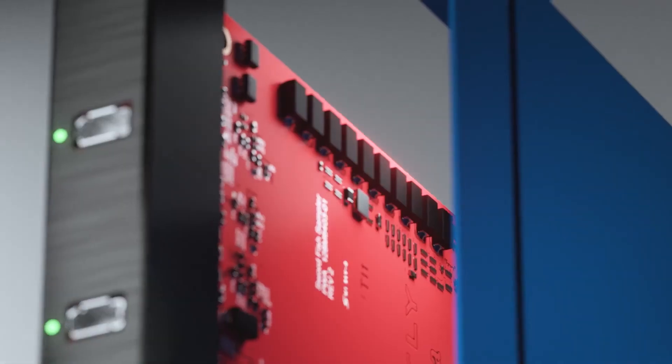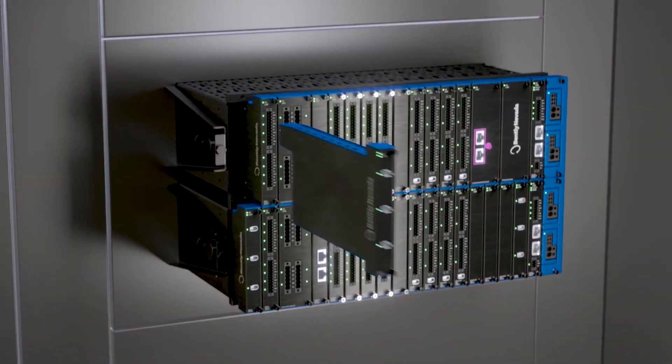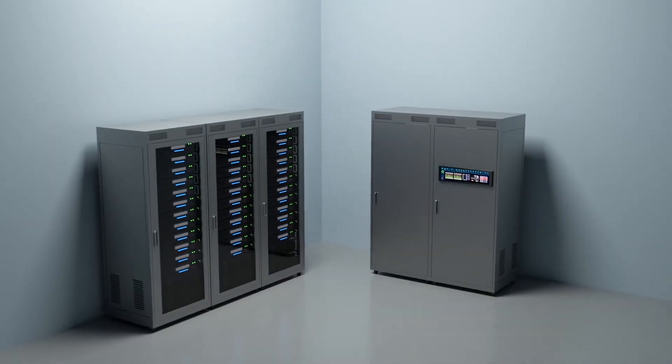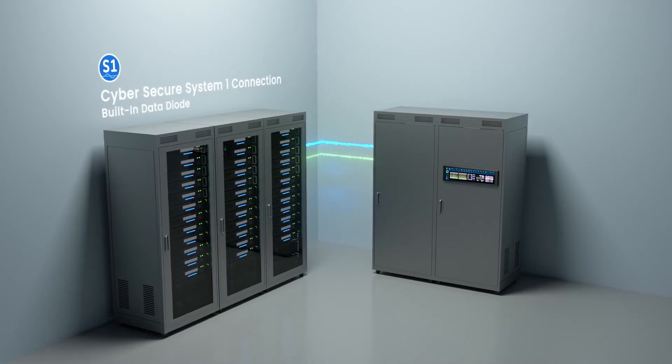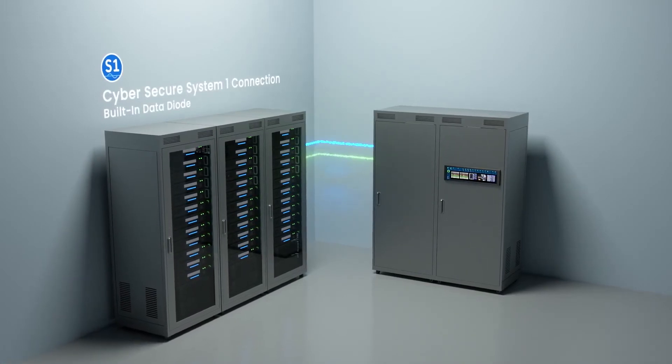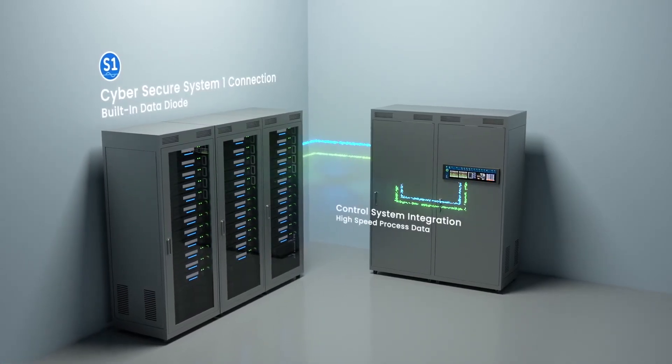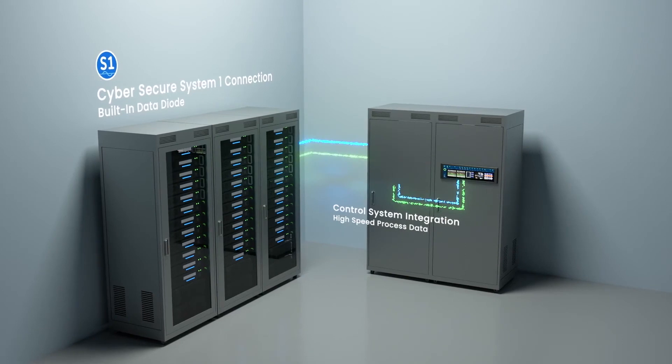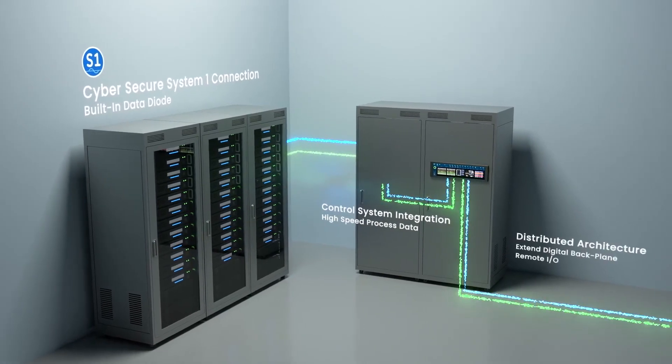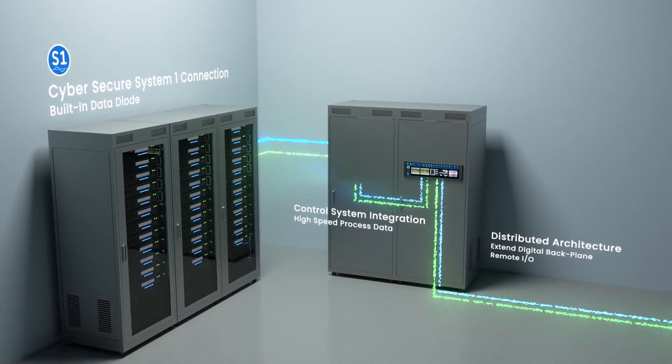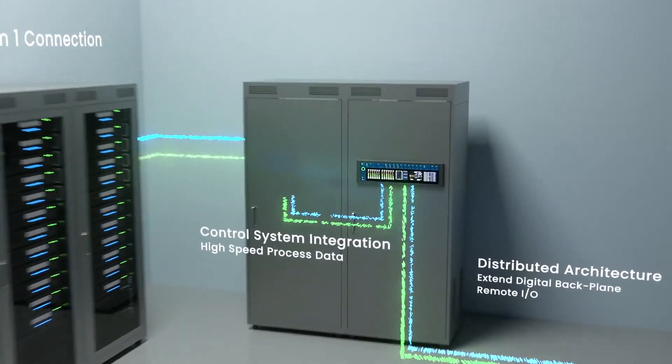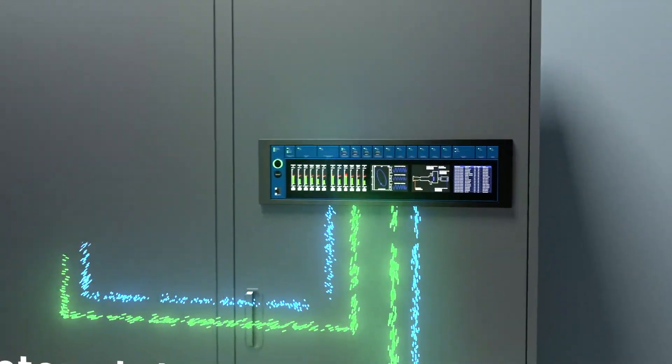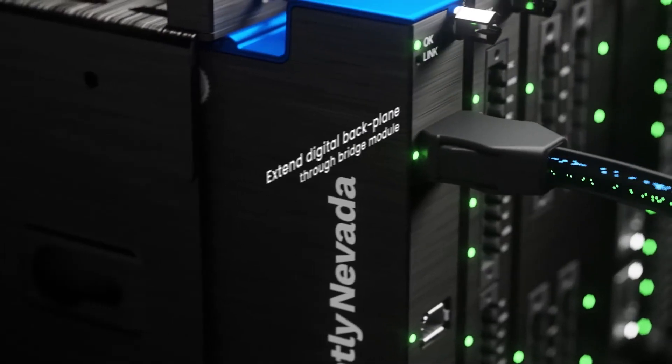Yeah, so very much thought was put around the retrofit side of an existing system. And so as you talked about earlier on the power supply side, we have removed the internal power supplies out of the Orbit 60 and there's just power input modules which are 24 volt DC. So on the back side of the 6U chassis, we have within that envelope of what a 3500 would have been, we can mount the power supplies, external power supplies right within that same space.